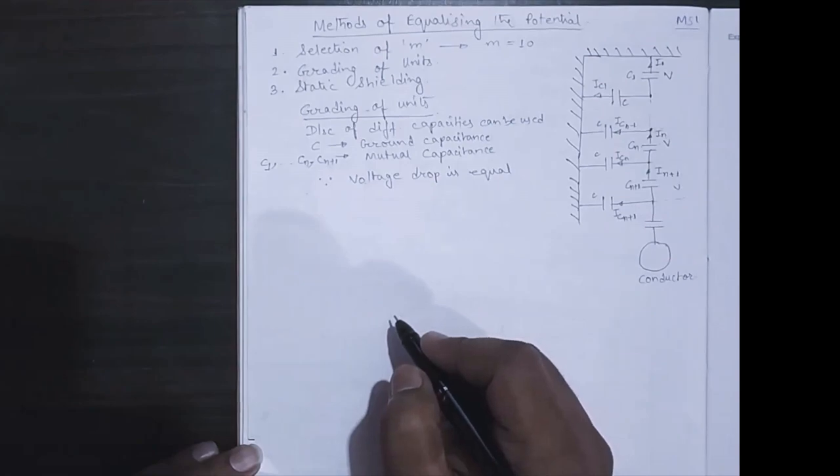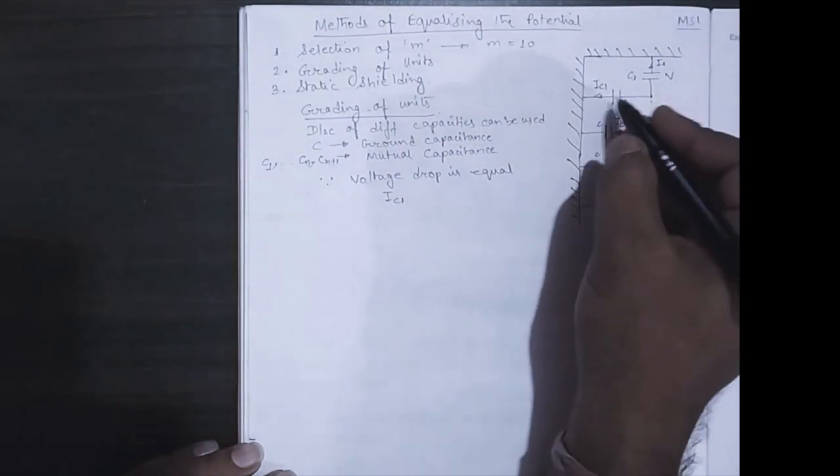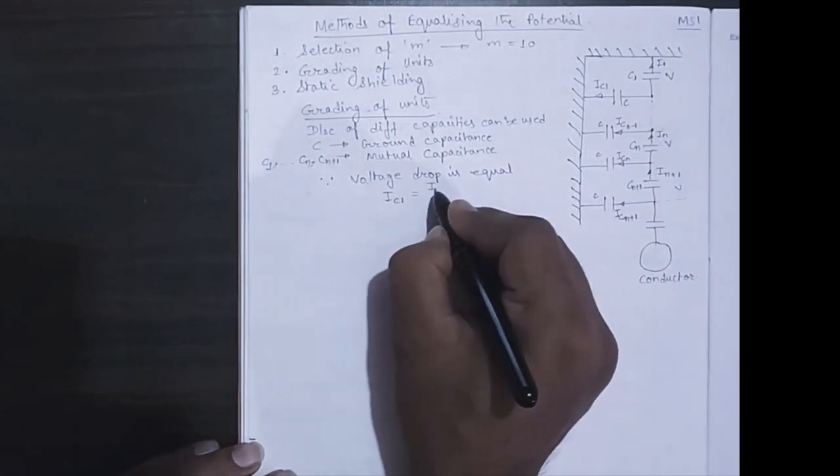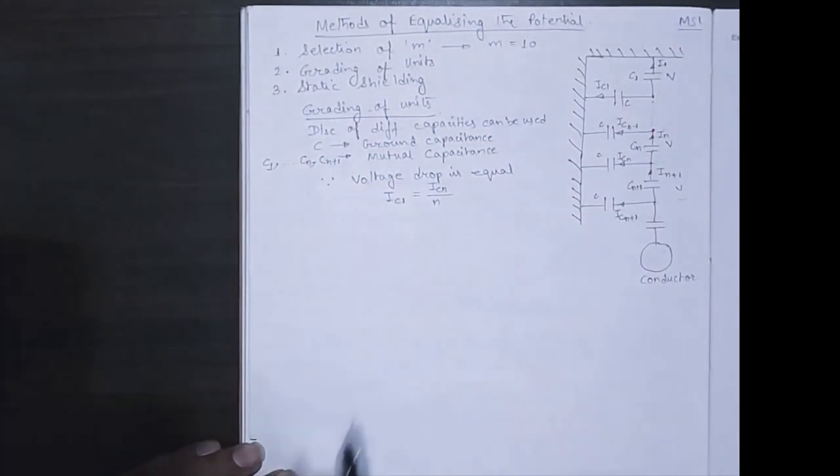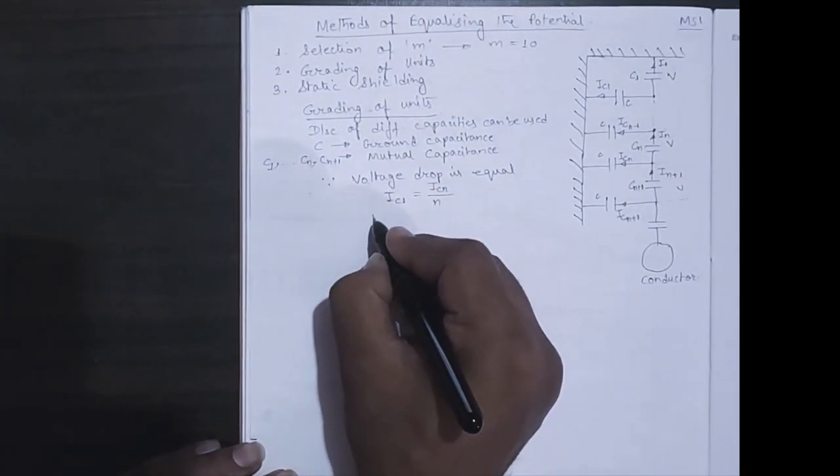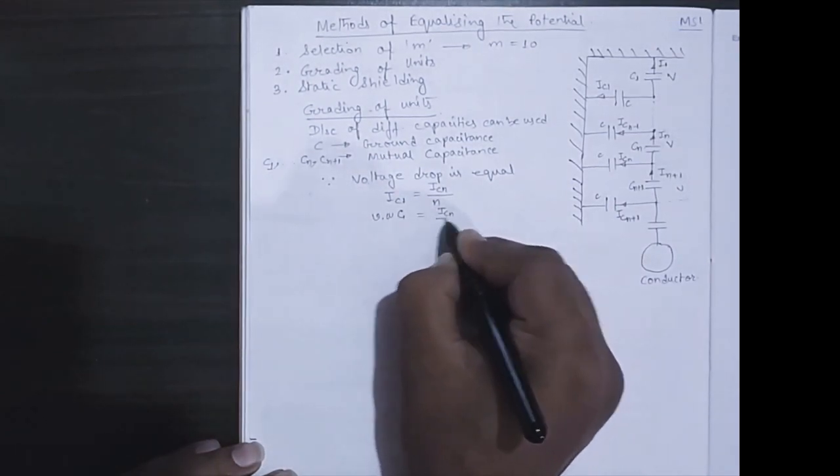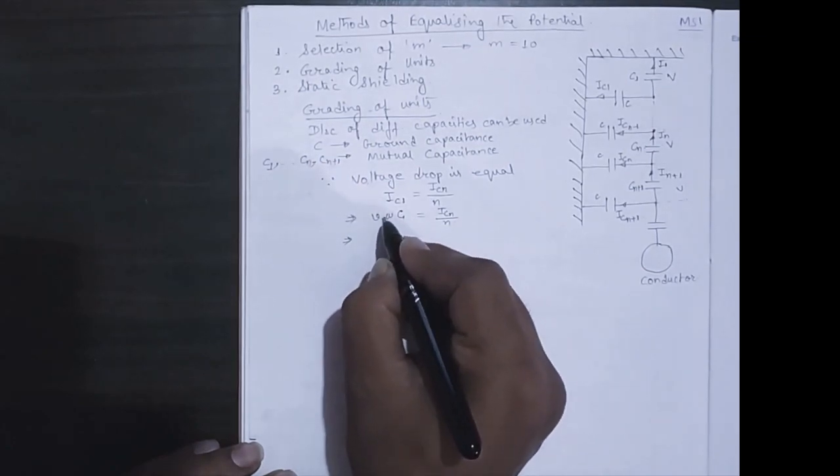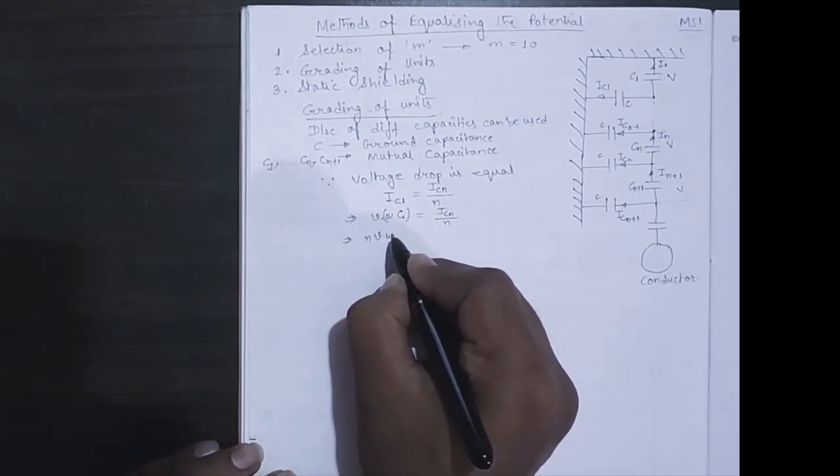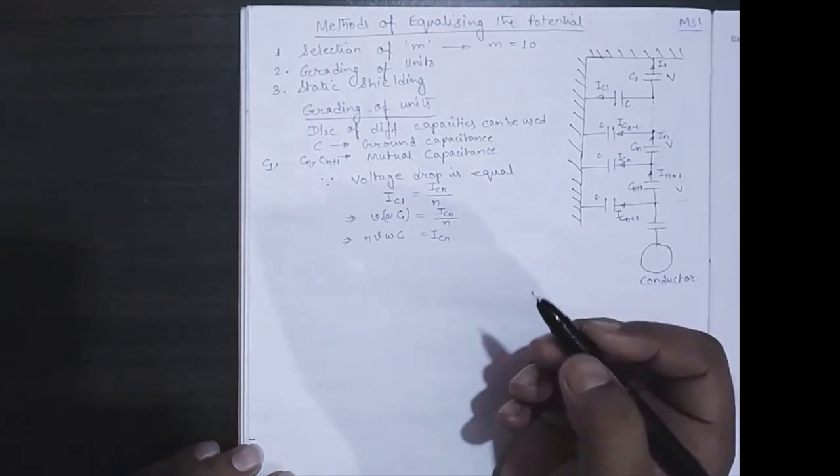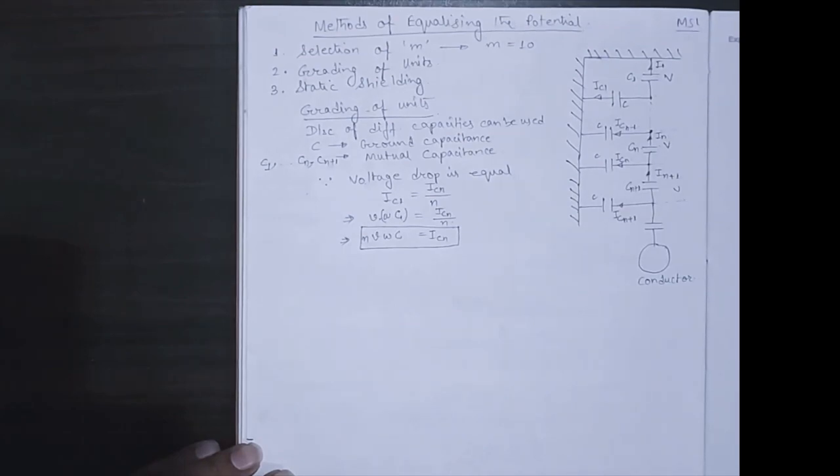Since voltage drop is equal between all insulator plates, the total current ic1 is equal to icn by n. We are taking that n number of capacitances are present, so total current is icn by n. Now ic1 can be written as v omega c. This is equal to icn by n. So icn can be written as n v omega c. This is equal to ic. This is important for this derivation.